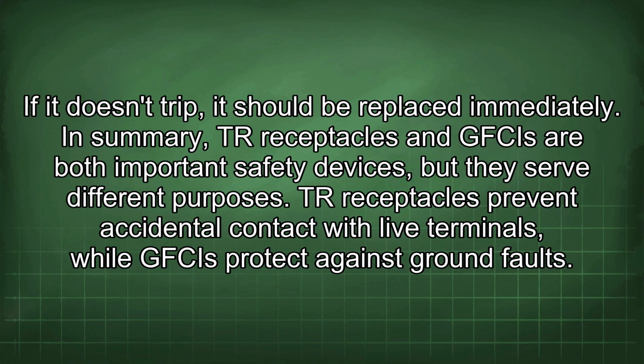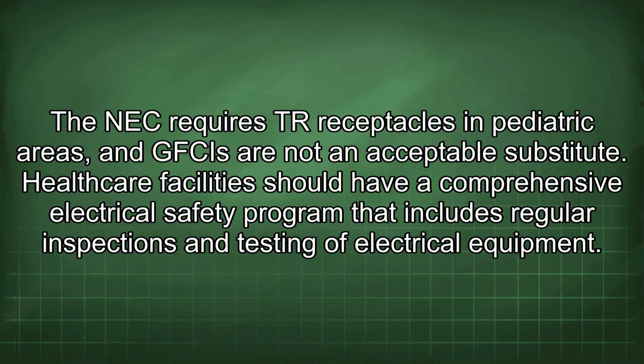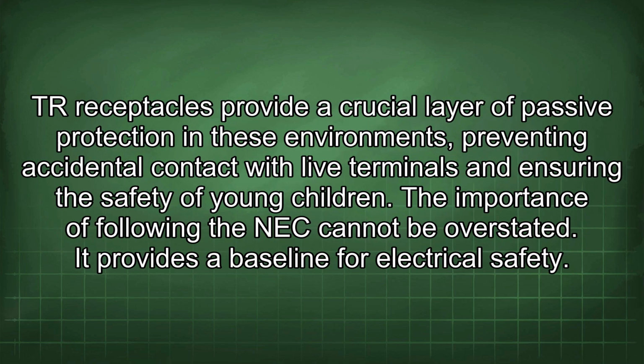In summary, TR receptacles and GFCIs are both important safety devices, but they serve different purposes. TR receptacles prevent accidental contact with live terminals, while GFCIs protect against ground faults. The NEC requires TR receptacles in pediatric areas, and GFCIs are not an acceptable substitute. Healthcare facilities should have a comprehensive electrical safety program that includes regular inspections and testing of electrical equipment. TR receptacles provide a crucial layer of passive protection in these environments, preventing accidental contact with live terminals and ensuring the safety of young children.